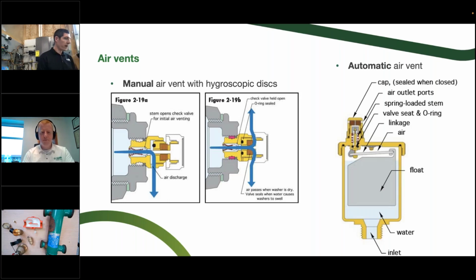Okay, now let's talk about the automatic air vent. This is going to be on the top of a lot of our different products here. We've got the linkage kind of pulled apart so you can see it a little better. So it comes out of the separator like that, comes out of the air vent. And then let's say you start to notice that there's a little bit of water coming out of the top of that. We've got a couple different options for you here. One could be that there's just a little copper shaving or piece of Teflon right in that needle right there. That's where you're going to find something that would hold that up from sealing well and keeping the air from leaving, or to allow water out of the air vent.